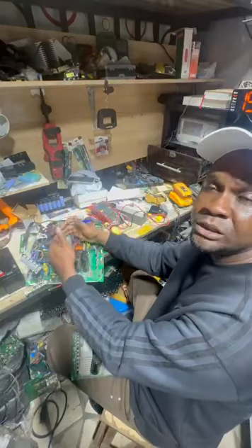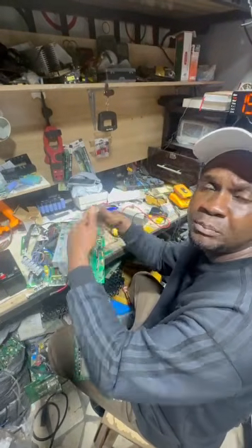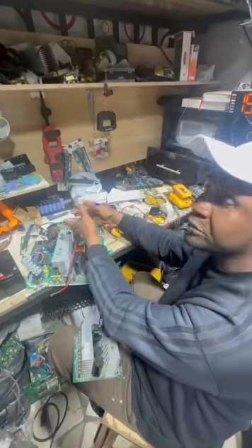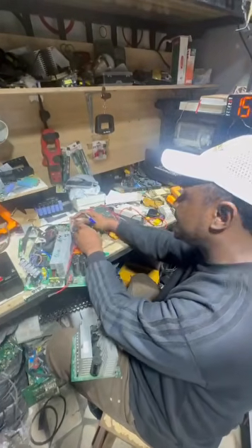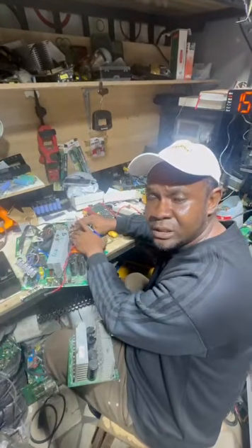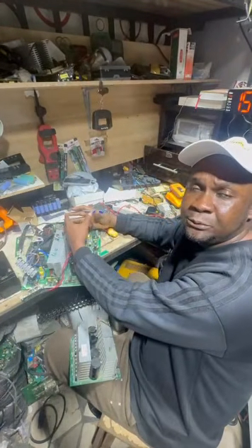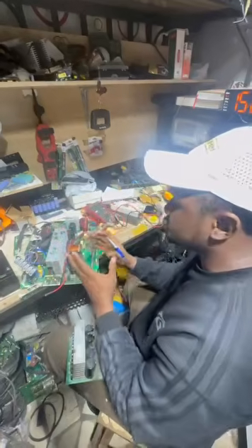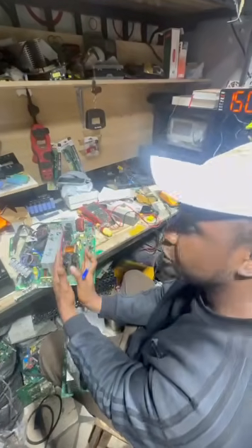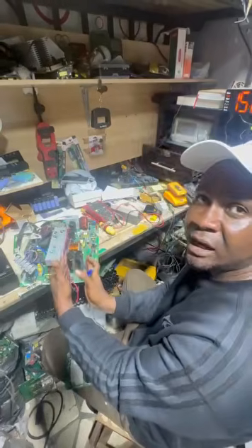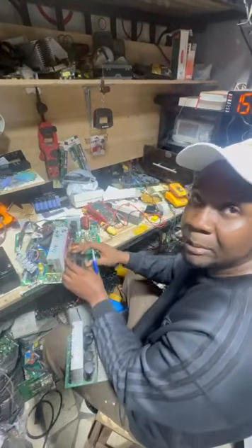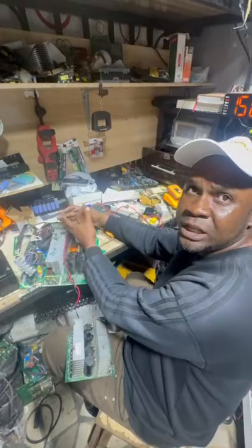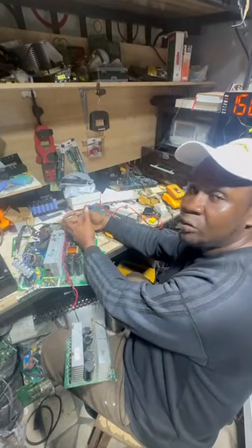So what will happen is that the AC output voltage is converted back to DC. The DC generated at that point will be stored in the reserve section where you have the capacitor. The capacitor here is rated around 400 volts to have the storage capability for the voltage converted from AC back to DC. The storage unit for the battery section is closer to the battery terminal. So this is the capacitor for the battery reserve. This is the capacitor for the high DC voltage reserve, which is called the power factor correction DC.